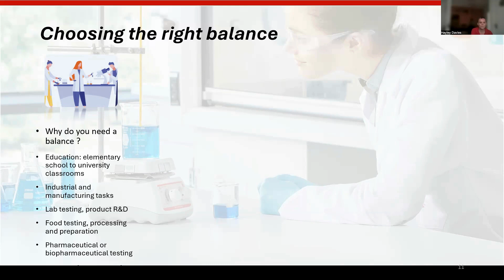What level of precision do you need? You've got your semi-micro and your analytical balances, which are 0.01 and 0.1 milligram respectively, or in old money, 5 decimal place or 4 decimal place. These have a high degree of accuracy and precision. However, they do need a really stable environment to get accurate measurements. With a precision balance, that's 1 milligram to 0.1 gram, you can get high capacities, and generally they are a bit more robust than the semi-micro or the analytical, but they are less precise.